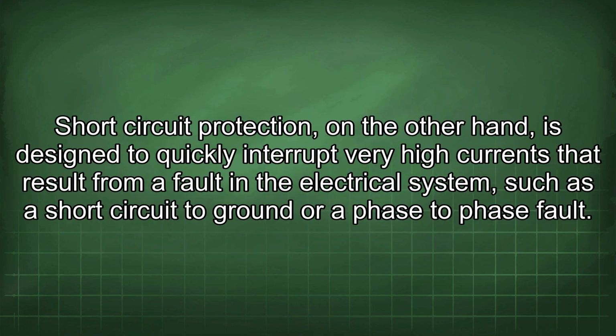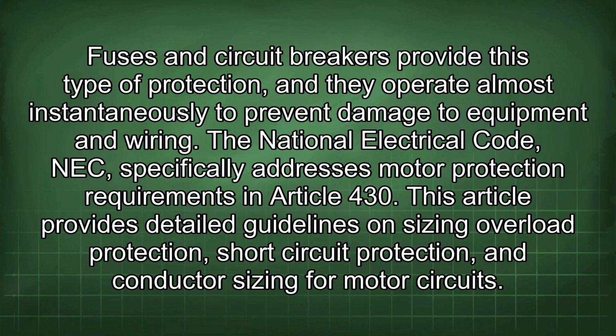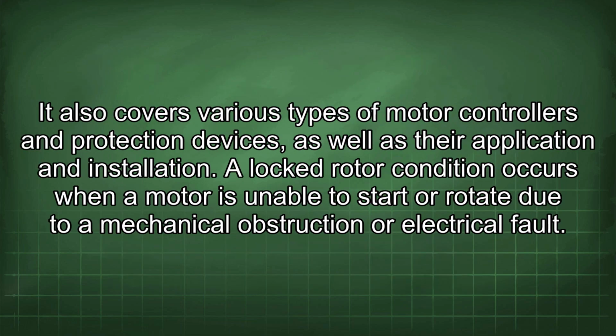Short-circuit protection, on the other hand, is designed to quickly interrupt very high currents that result from a fault in the electrical system, such as a short circuit to ground or a phase-to-phase fault. Fuses and circuit breakers provide this type of protection, and they operate almost instantaneously to prevent damage to equipment and wiring. The National Electrical Code, NEC, specifically addresses motor protection requirements in Article 430. This article provides detailed guidelines on sizing overload protection, short-circuit protection, and conductor sizing for motor circuits. It also covers various types of motor controllers and protection devices, as well as their application and installation.